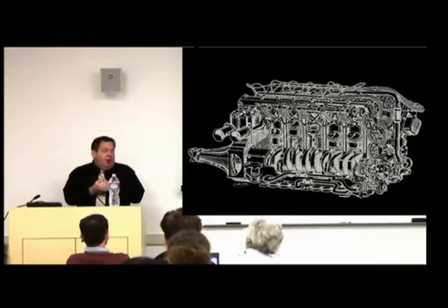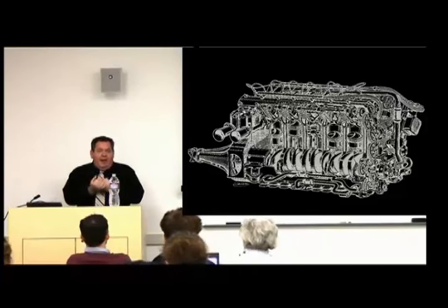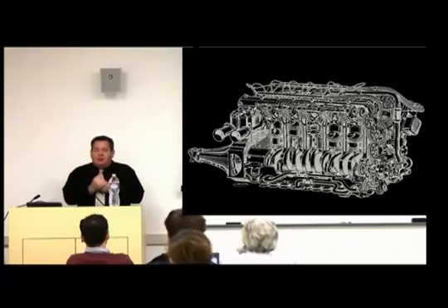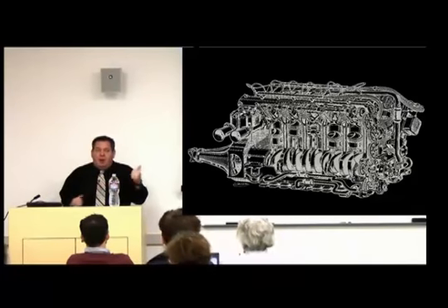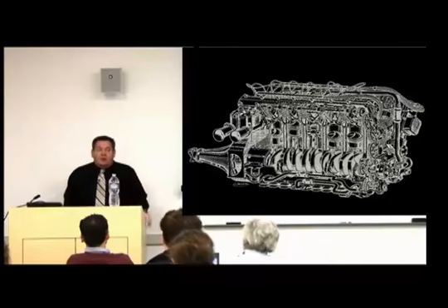Minimize means we're going to put operational limits. Reduce emissions means numeric emission values. Oftentimes that's going to require a catalyst from internal combustion engines at major sources and area sources. And it's the onus of the owner-operator to demonstrate initial and continuous compliance.